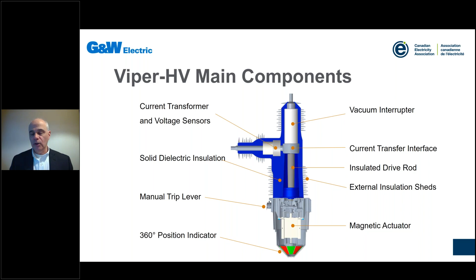I'll share with you briefly some of the ratings. We've dispatched solutions from 40 kV to 72.5 kV. Our initial release is at 1200 amps continuous current, with another solution due out shortly having 2000 amp capability. The fault interrupting ability is all the way up to 31.5 kA for this particular product. So very powerful interrupting capability embedded with this solution.